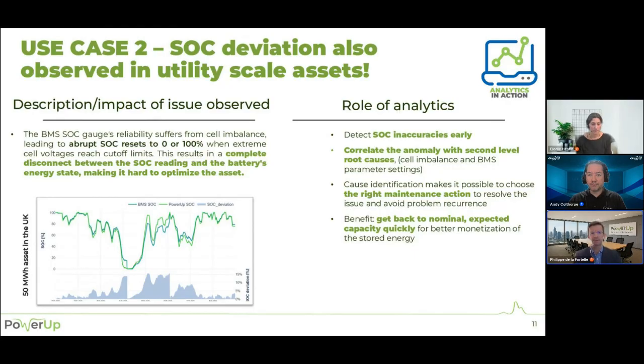And there again, battery analytics provides root causes or ways to improve the SOC accuracy, recalibrating the BMS or understanding the cause of such BMS inaccuracies in the first place, and getting back to nominal expected measurement capabilities. So that is for a problem of SOC inside a rack.